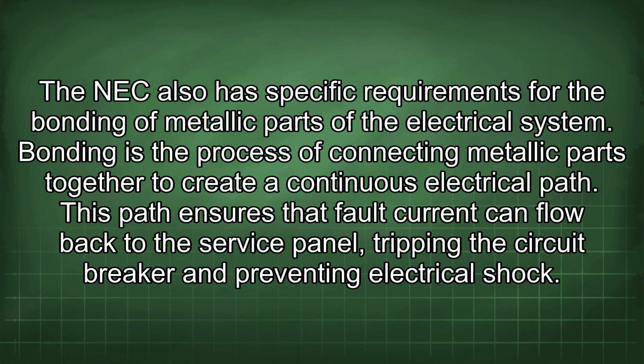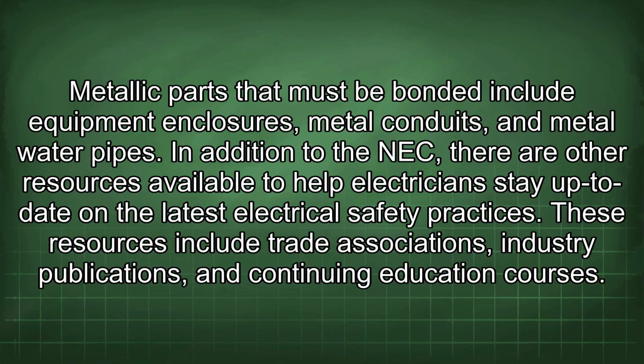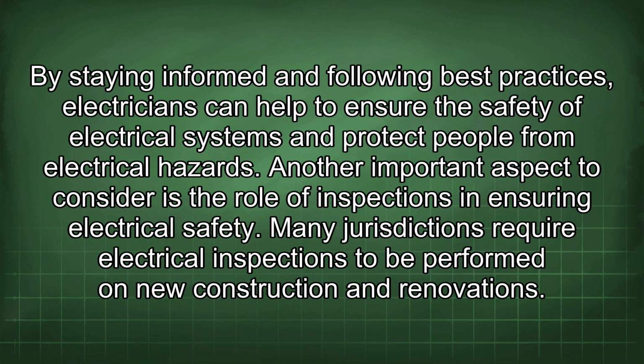Bonding is the process of connecting metallic parts together to create a continuous electrical path. This path ensures that fault current can flow back to the service panel, tripping the circuit breaker and preventing electrical shock. Metallic parts that must be bonded include equipment enclosures, metal conduits, and metal water pipes. In addition to the NEC, there are other resources available to help electricians stay up to date on the latest electrical safety practices. These resources include trade associations, industry publications, and continuing education courses.